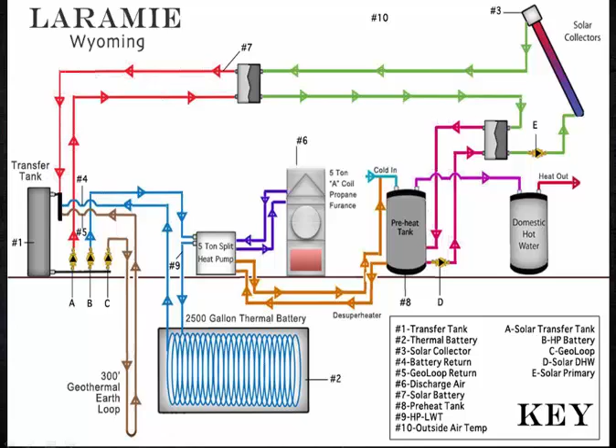That particular tank is not referencing what's going on in the tank—there's another sensor that goes in tank number 2. But yes, basically that would be your hydraulic separator in the system, albeit done with just two pipes. It's just an intermediary, a wide spot in the road for everything to tie together and for those temperatures to blend—what Siggy would call a fat spot in the road.